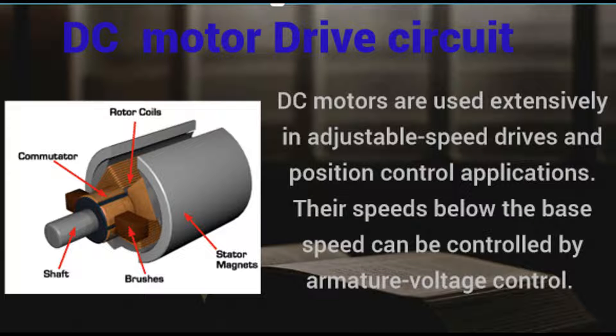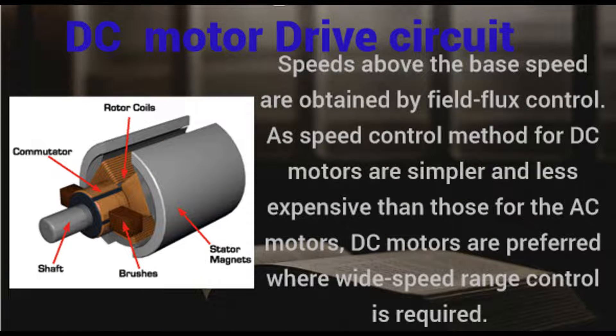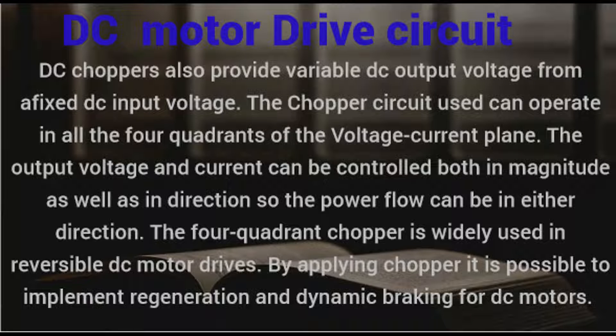DC motors are used extensively in adjustable speed drives and position control applications. Their speeds below the base speed can be controlled by armature voltage control, while speeds above the base speed are obtained by field flux control. Speed control methods for DC motors are simpler and less expensive than those for AC motors, making DC motors preferred where wide-speed range control is required. DC choppers provide variable DC output voltage from a fixed DC input voltage, and the chopper circuit can operate in all four quadrants of the voltage-current plane, allowing power flow in either direction. The four-quadrant chopper is widely used in reversible DC motor drives, enabling regeneration and dynamic braking.